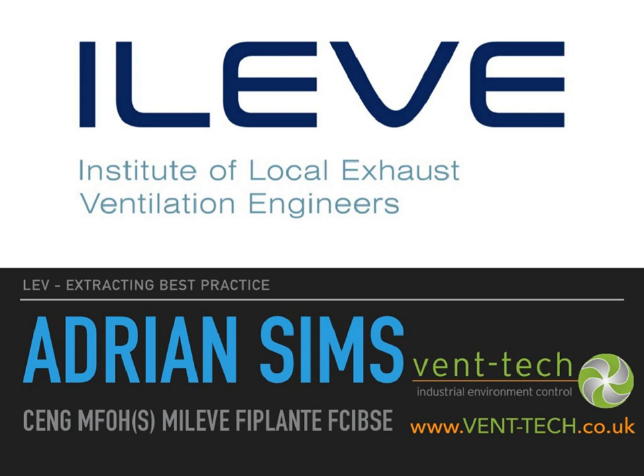The big issue doing work on boats - and we're doing some work on ships at the moment - is space. There's a real lack of space on vessels to get the ducting in and out, so you tend to have relatively small ducts, meaning your volume flow is squeezed through a small pipe, giving you much higher velocity. Higher velocities bring noise, but noise isn't always the big issue on ships - it's more the kilowatt rating of the motor needed to overcome those additional pressures generated by squeezing the air through the pipe.